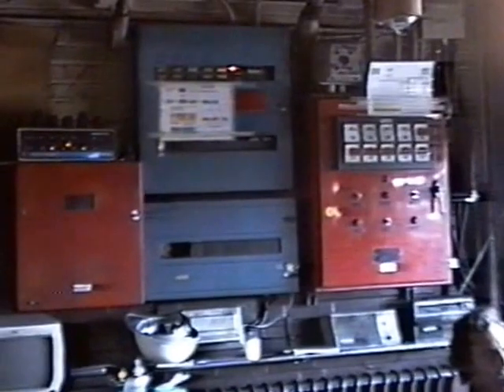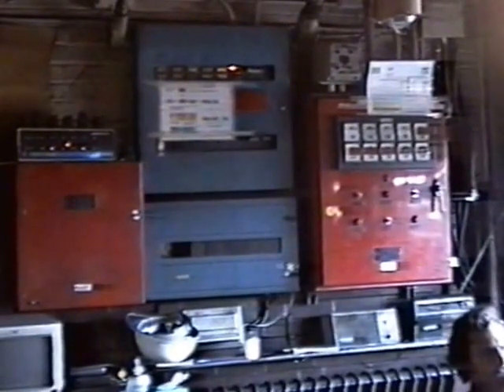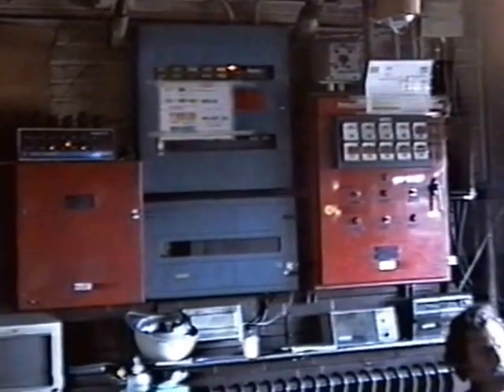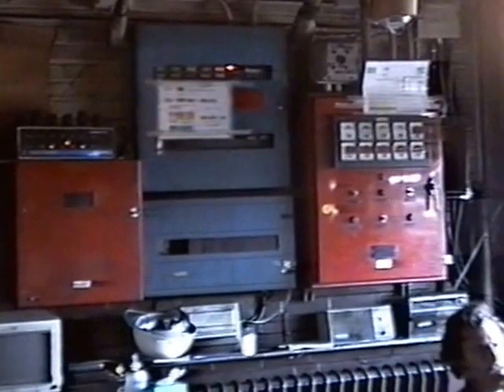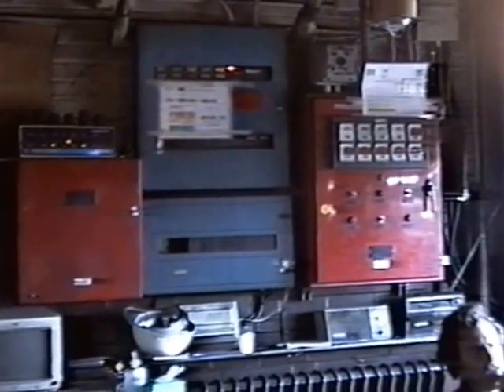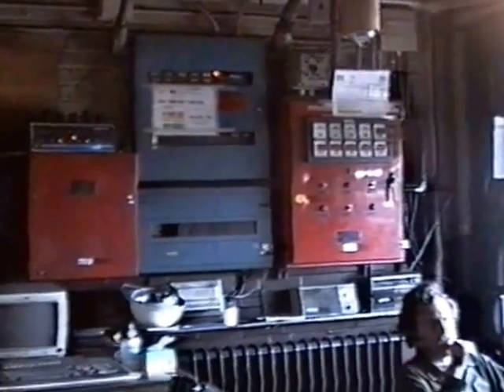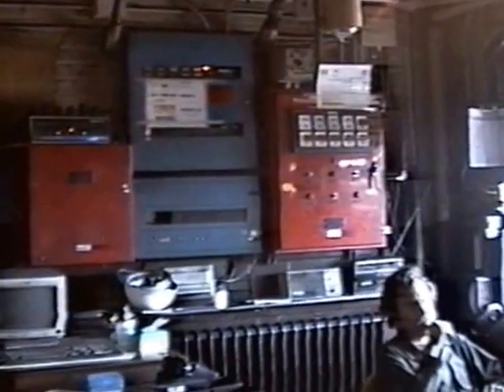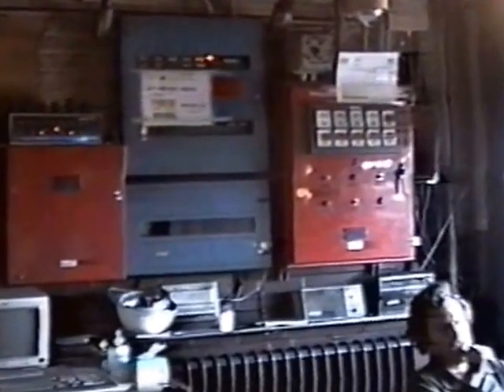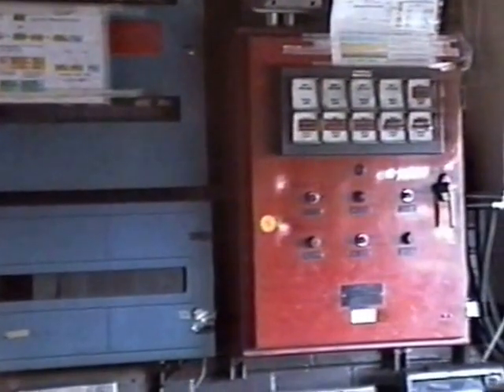Should an alarm come in for one of those systems, the diesel pump automatically starts and supplies water to those systems. If the diesel fire pump starts, as we said before, it's necessary that someone go down and check it to make sure that the pump is running properly and does not turn off for any reason except turning it off manually by the button that we've looked at before.